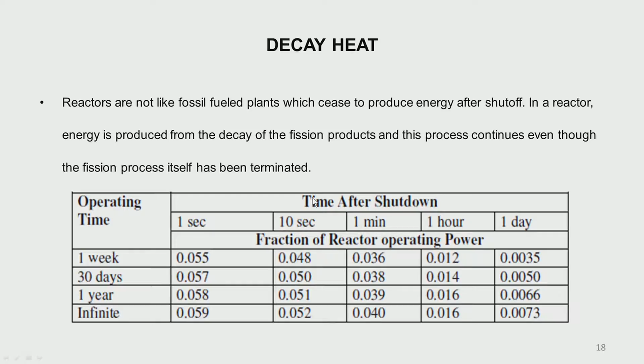To give you an idea, it depends on how much the reactor is operated, because the amount of time the reactor is operated shows how much fission product accumulation is there, and how much time after the shutdown, both these factors. So, here if you look, let us say a reactor is operated for 1 week and after shutdown it will produce about 5.5%, slowly in 1 day it will come down to 0.35%. Suppose it is operated for a year, it will be about 5.8%, then about 0.66% here. So, slowly it will come down. Now, this means heat is continuing to be produced even after shutdown. So, this aspect is very important to be recognized.